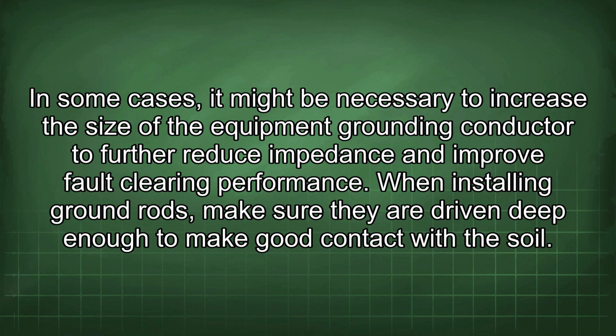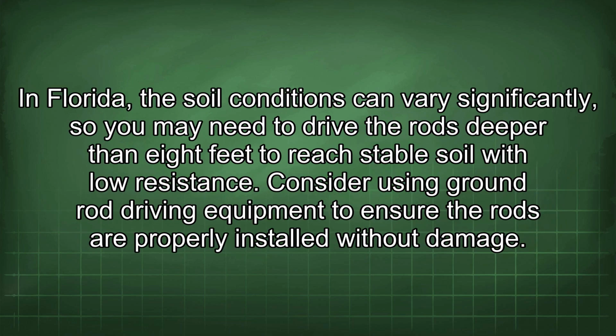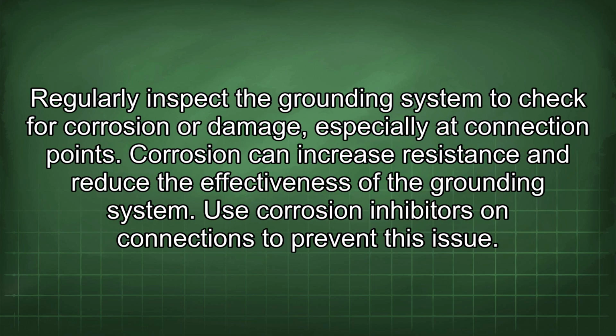When installing ground rods, make sure they are driven deep enough to make good contact with the soil. In Florida, the soil conditions can vary significantly, so you may need to drive the rods deeper than 8 feet to reach stable soil with low resistance. Consider using ground rod driving equipment to ensure the rods are properly installed without damage. Regularly inspect the grounding system to check for corrosion or damage, especially at connection points. Corrosion can increase resistance and reduce the effectiveness of the grounding system. Use corrosion inhibitors on connections to prevent this issue.